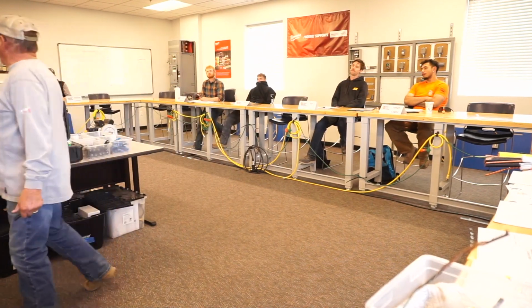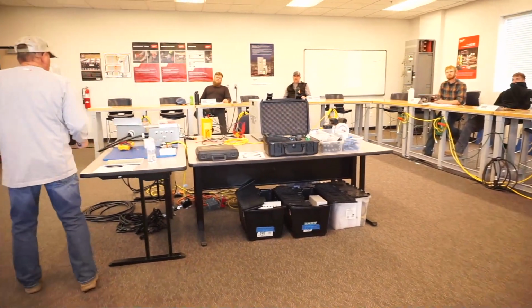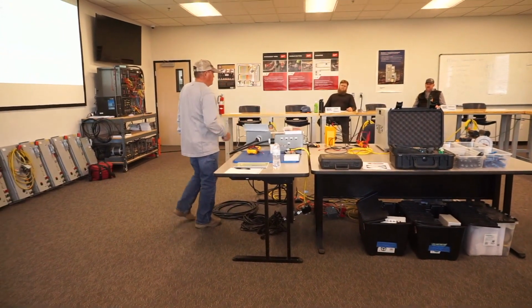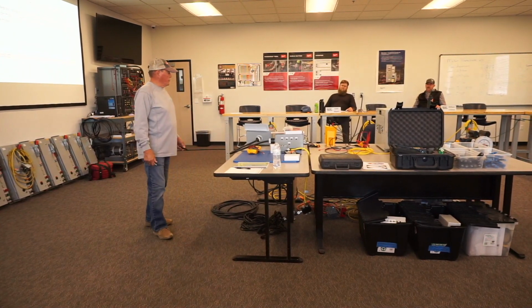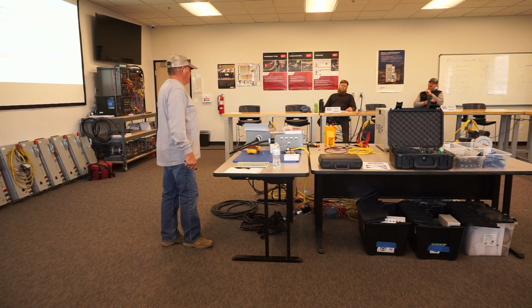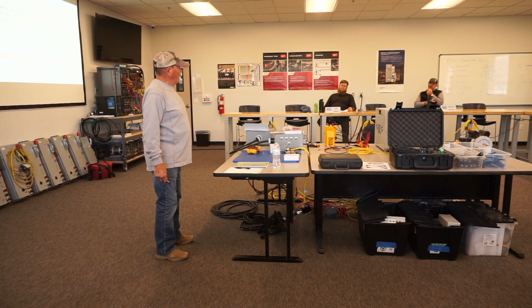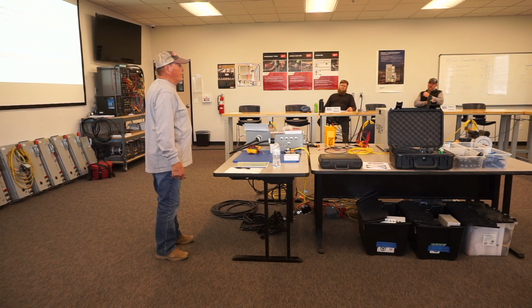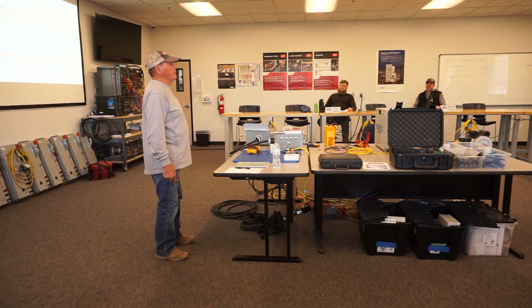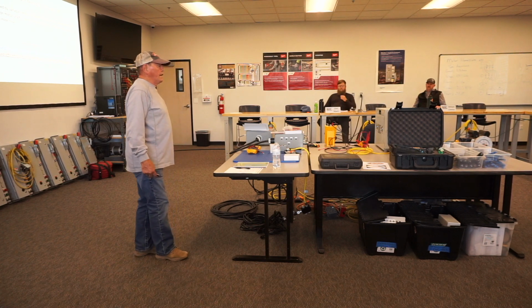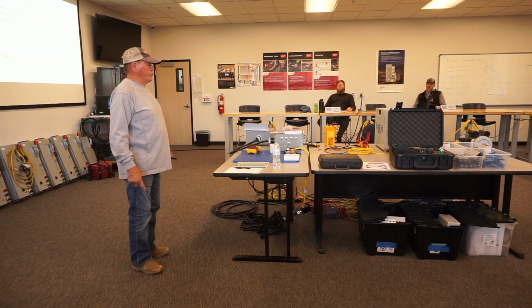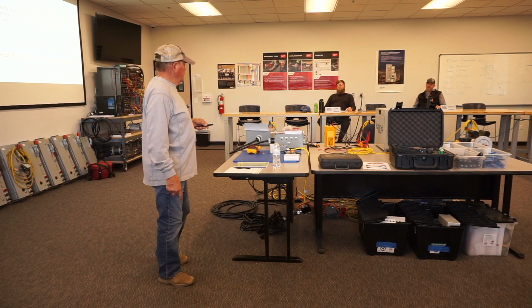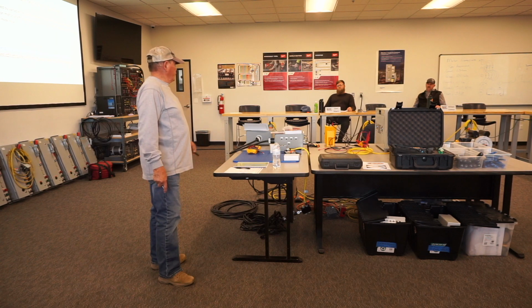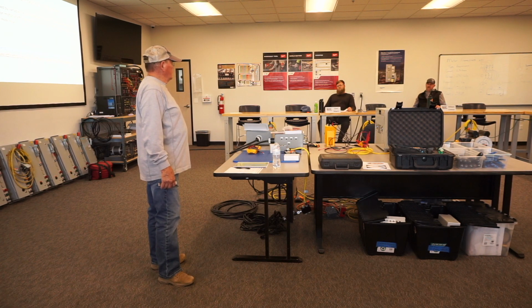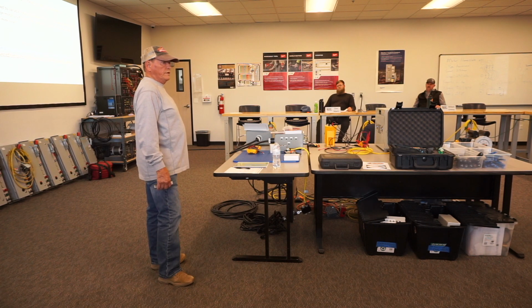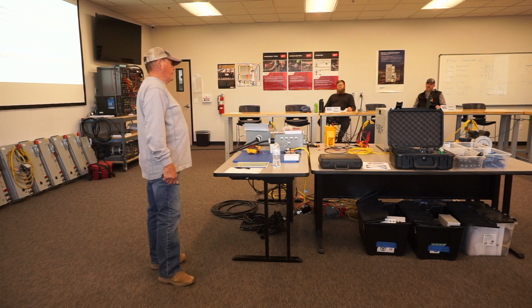I had never seen them before, knew nothing about them, but they had boxes of these that they were going to put on the drives because they kept losing motor bearings. I actually saw it at that hospital in Dallas on the brand new chiller that had been brought to the project. In that chiller were those devices. The Carrier chiller had a variable speed drive on it, and the output of that drive had those on it. And whoa, Carrier thinks that much of it, there must be something to it. So the hospital bought a bunch of them, and they're going to put them on the output of their drives.